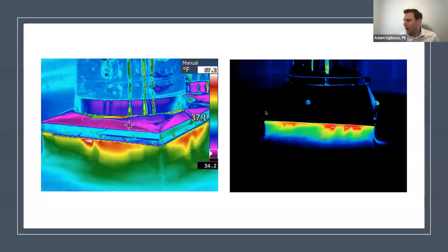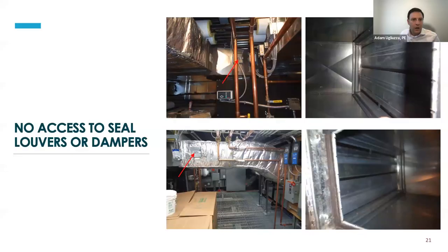And here's an example why. This is an infrared scan of that interface between the ductwork and the curb. Tremendous amount of air leakage. If you've got a lot of penetrations up through the roof, this could happen at every single one of them, so that's something to keep in mind too. If the building's failing, this might be a significant air leakage source that can easily be addressed, but you have to make sure you find it.